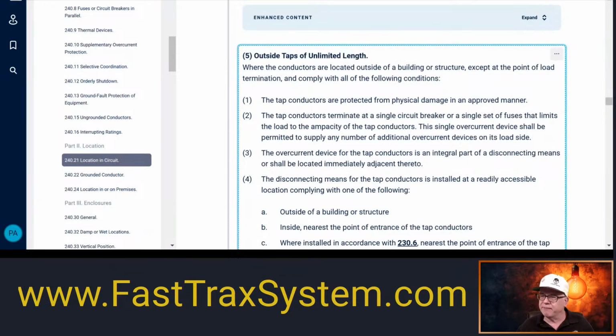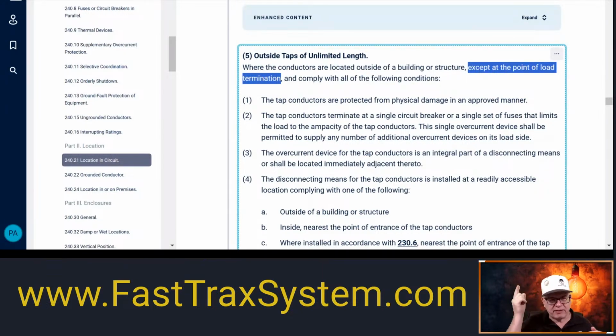All right, outside. This is where a connection is being made to a feeder, and this is outside of the building, what we consider outside of the envelope. It says where the conductors are located, and they're talking about the taps, where the conductors are located outside of a building or structure, except at the point of load termination. Obviously they have to come back into the building if it's a tap connection made outside, which is very common to make in big buildings.